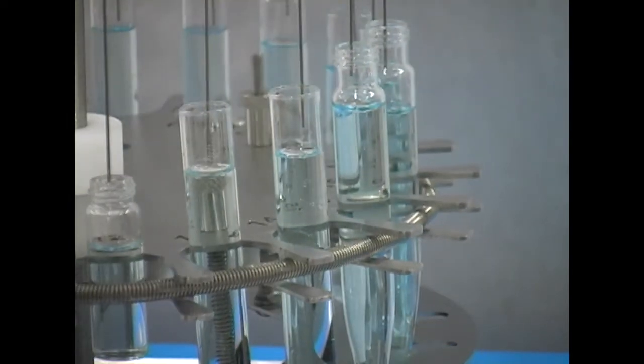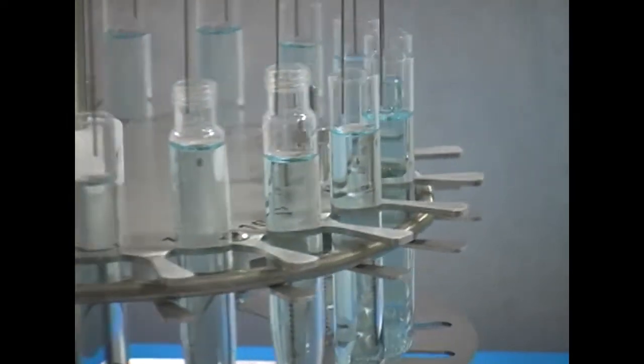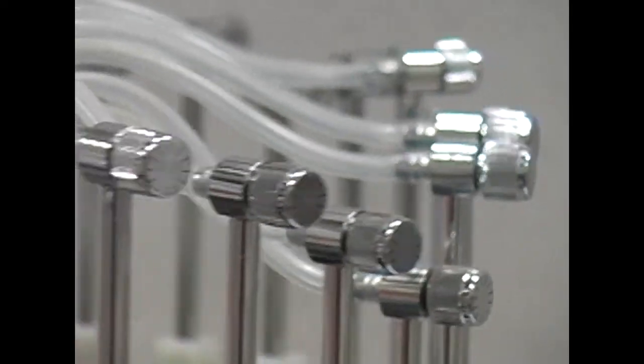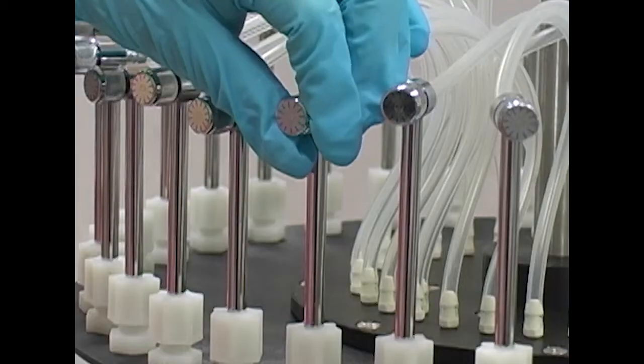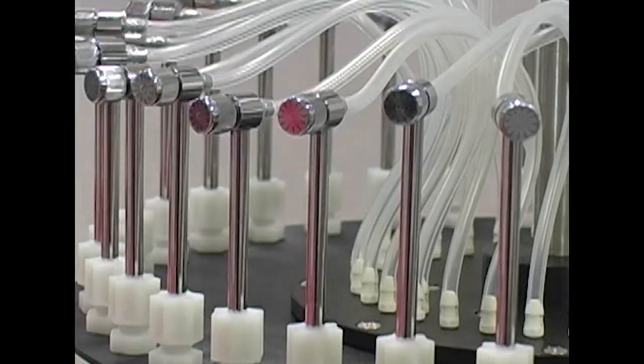Compared to other evaporators on the market, no additional racks or accessories are needed. The user is in full control of the nitrogen flow delivered to each sample due to our classic chrome-plated needle valves.